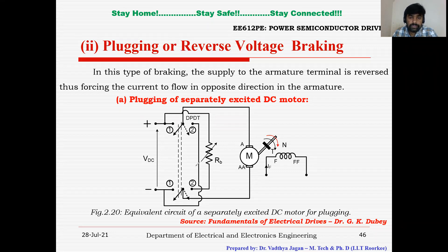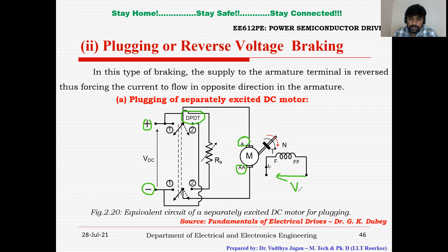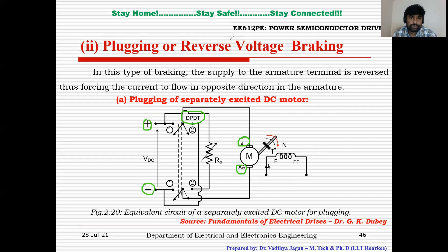You can see the equivalent circuit of a separately excited DC motor during plugging. The armature consists of terminal A, which is connected to the VDC through the DPDT switch. The field is connected to a separate DC source, V2. Since V2 is constant for a fixed field resistance, the field current will be constant and therefore field flux is also constant. We are not discussing the field part further as it provides a constant field current due to the constant field voltage.